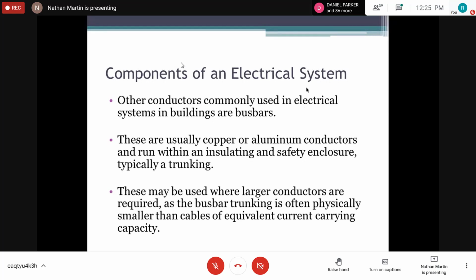These may be used where larger conductors are required, as the bus bar trunking is often physically smaller. So rather than have this whole heap of big SWA cable or large cross-sectional area cables running, they actually use the bus bar trunking for aesthetic purposes. All right, so it's just some bars, rather than having the 3 cables in a SWA or 4 core SWA cable.